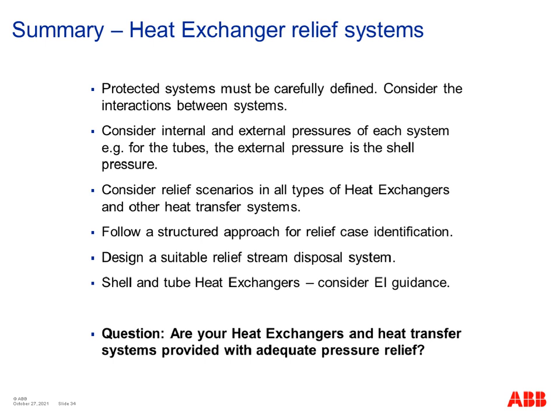So the more general summary now. For heat exchanger relief systems, the protected systems must be carefully defined, and always consider the interactions between those systems. Consider the internal and external pressures of each side of the exchanger, each system. So for example, for the tubes, the external pressure would be the shell pressure, and of course for the shell, the external pressure would be the outside environment pressure. So think about those internal and external pressures and how they apply to which side of the system you're looking at. Consider relief scenarios in all types of heat exchangers and other heat transfer systems.